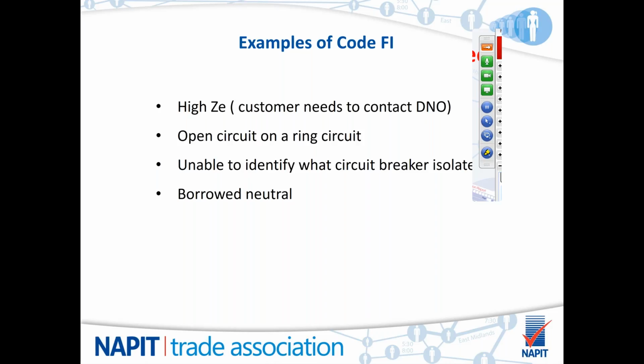So again, further investigation. And one of the most common problems we have, of course, is in the olden days, neutrals used to be borrowed for upstairs and downstairs lighting, and a borrowed neutral can cause problems when isolating, especially to the uneducated that don't check things are alive or dead. Therefore, isolating one circuit, you could still get a little bit of a backfeed on a borrowed neutral and get an electric shock. Again, further investigation.